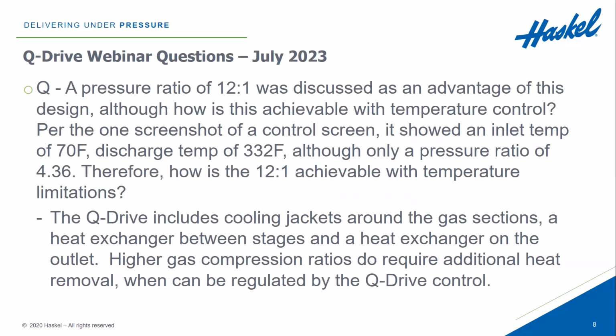Gas pressure ratio of 12:1 was discussed as an advantage of the design, although somebody's wondering how we can achieve that and maintain temperature control. They were looking at the screenshots that we were showing during the webinar, and it showed an inlet temperature of 70 and a discharge temperature of 332 with only a compression ratio of 4.36. How can we achieve 12:1?